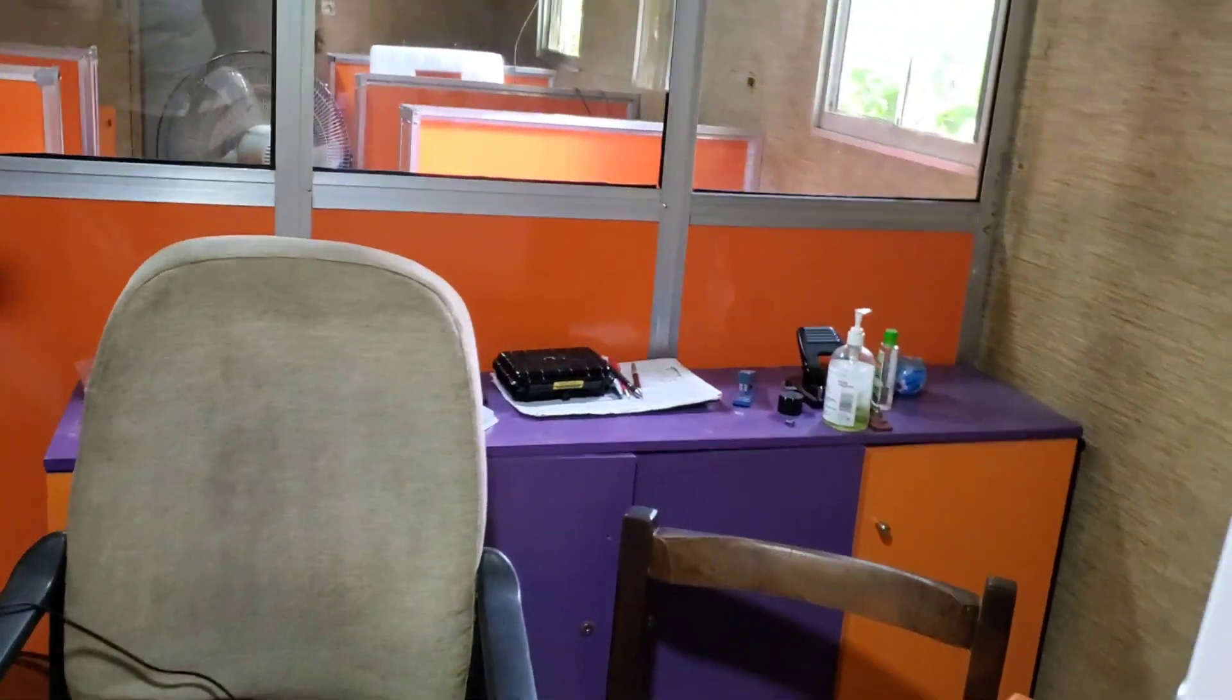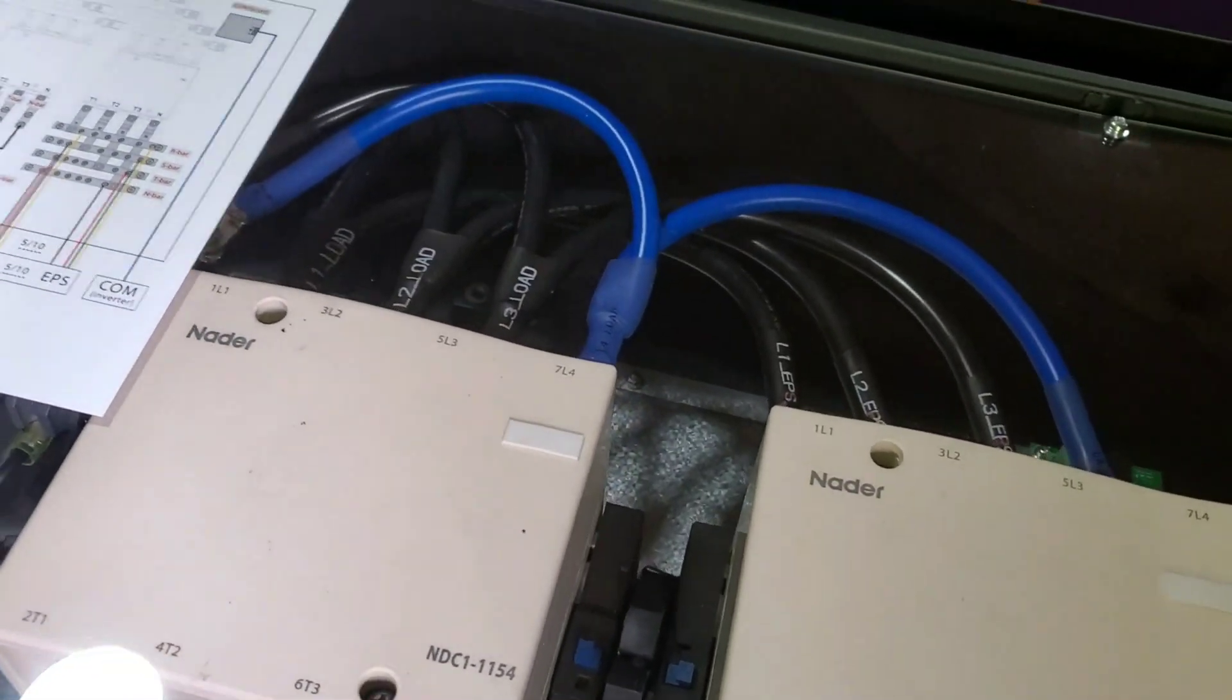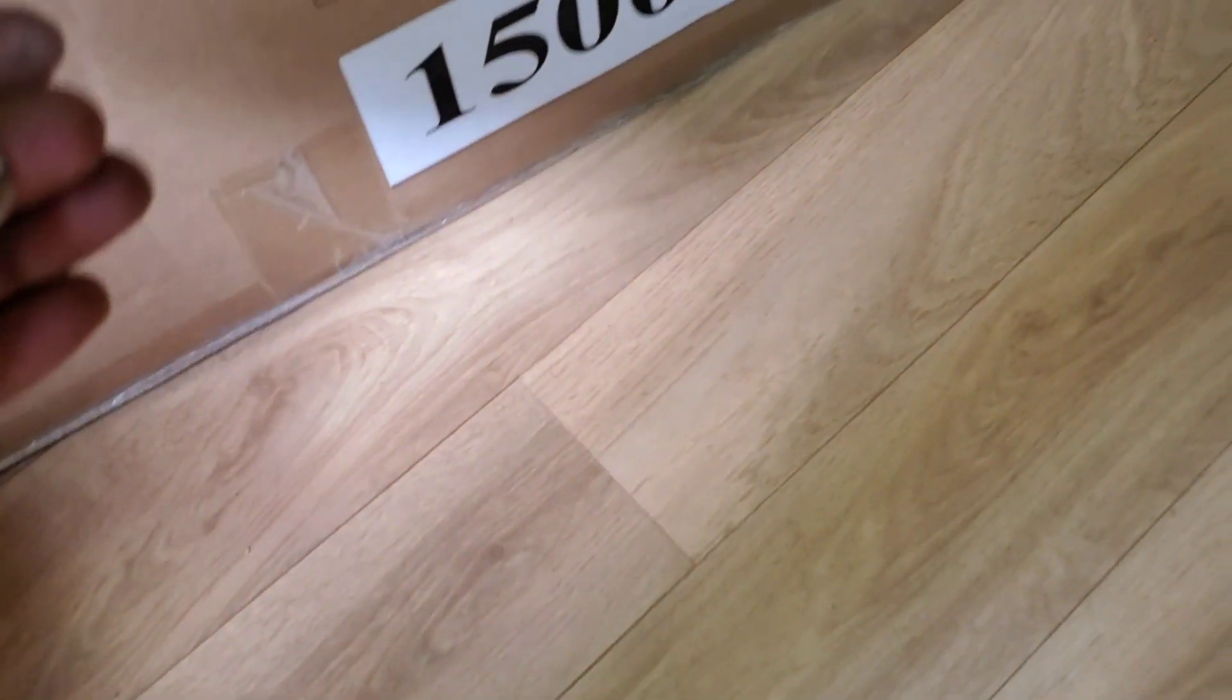Everything is IP65, it could be installed outdoors. Let me show you the front and then I'm going to open this sucker up. Let me back up so you see how big this thing is, it's pretty big. I mean it's huge. You can put up to five of the 15 kilowatt inverters into this sucker here, pretty impressive. One of the things that amazed me is the fact that they have 12 screws holding the cover in place. Twelve. They sure want to keep it very secure. I guess that's why it's rated IP65. There's the cover, and then they have earthed the cover to the chassis right there.